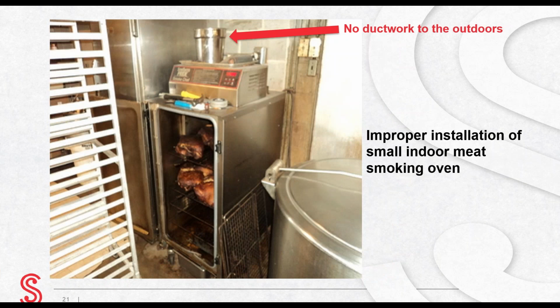This is an improper installation of a small meat smoking oven. This indoor meat smoking oven is not under a commercial kitchen exhaust hood designed for grease cooking. Recall that a small meat smoking oven does not have to be under an exhaust hood if it meets NFPA 96 Type 1 ductwork or vent piping to the outdoors. However, there is no vent piping on this oven, as pointed out by the red arrow. If there is a fire in the smoker, it could spread throughout the kitchen.